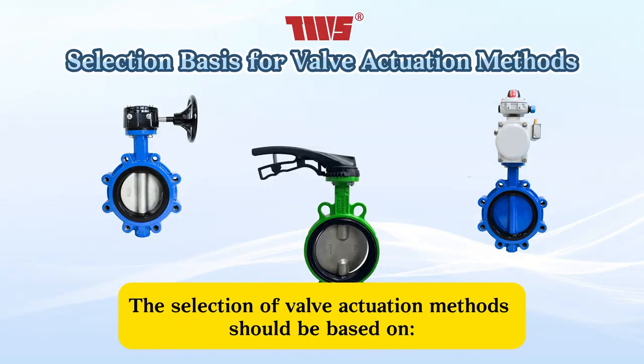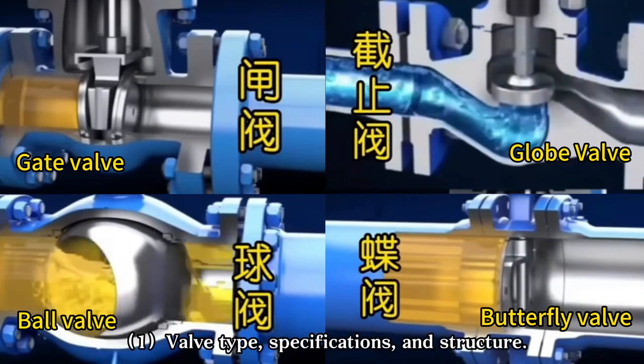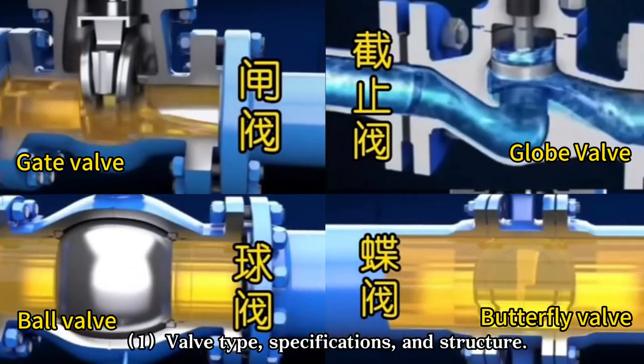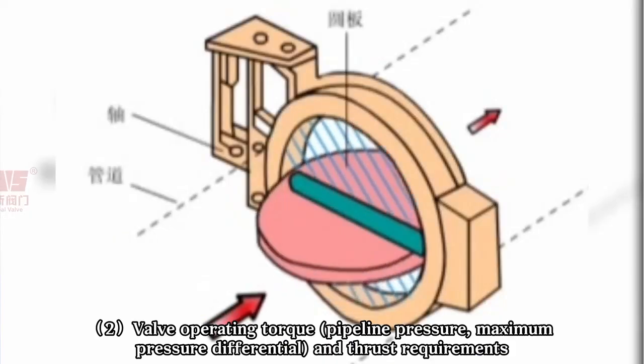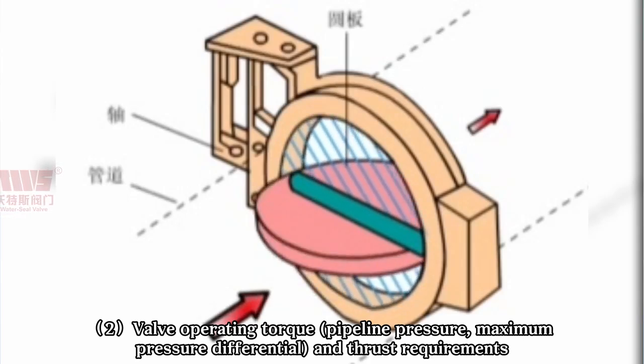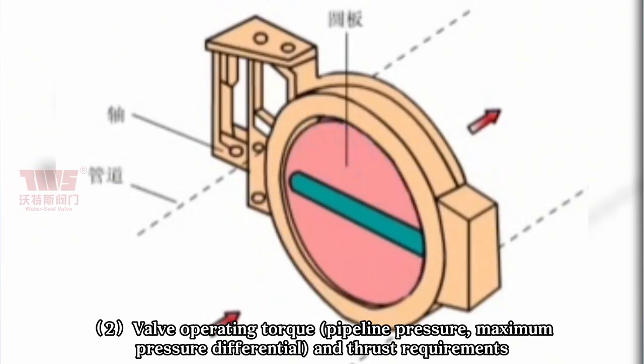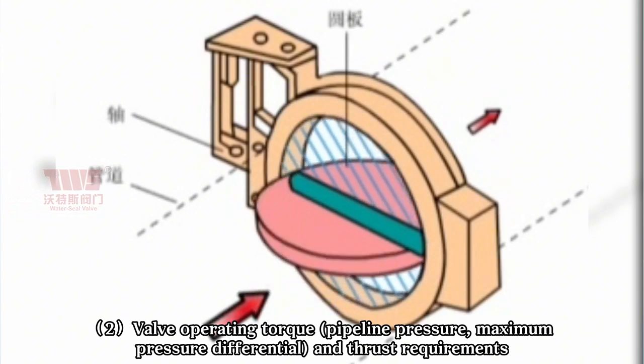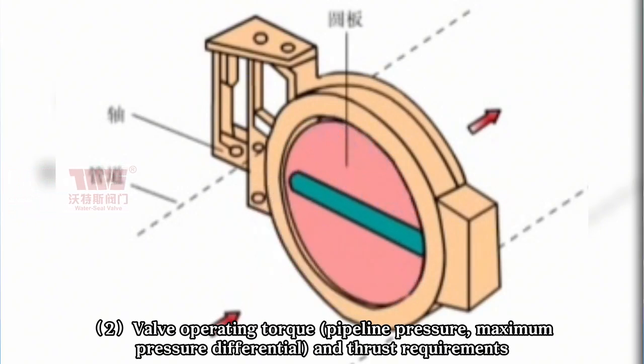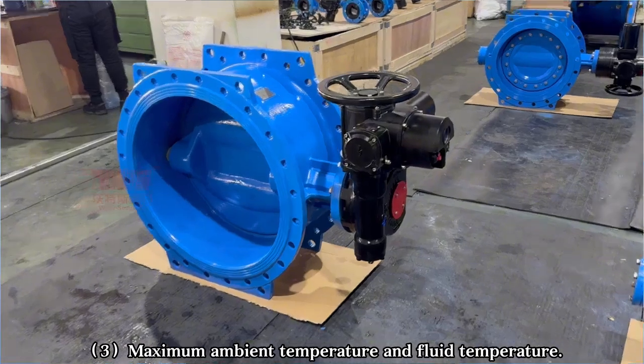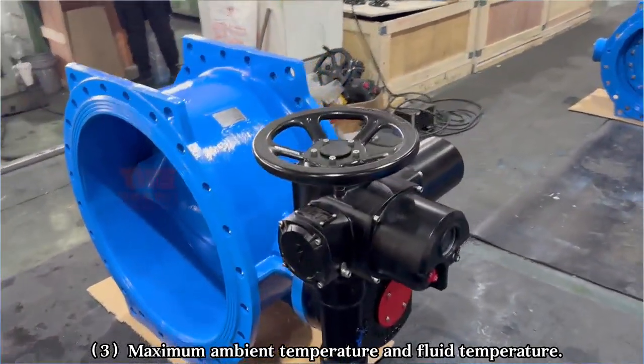The selection of valve actuation methods should be based on: 1. Valve type, specifications, and structure. 2. Valve operating torque, pipeline pressure, maximum pressure differential, and thrust requirements. 3. Maximum ambient temperature and fluid temperature.